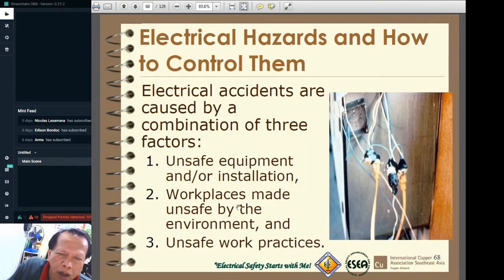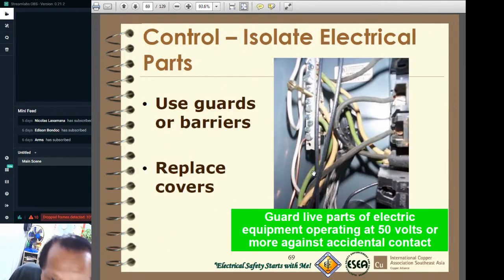No? Okay, this kind of installation is not correct because the wires are just simply flying, so it's dangerous. Somebody might touch it, or it might also cause deterioration of these wires. Okay, the splicing was simply done on the terminals of the plug, so it's not correct. Okay, electrical accidents are caused by a combination of three factors: unsafe equipment installation, workplaces made unsafe by the environment, and unsafe work practices. Okay, there are also installations that you would see are not properly done, magulo.